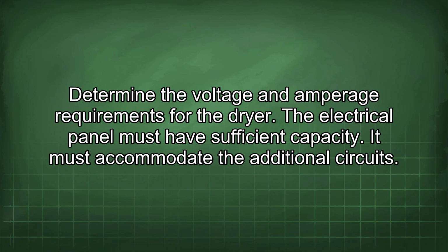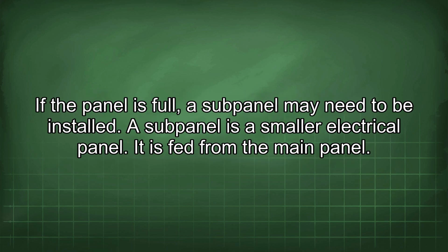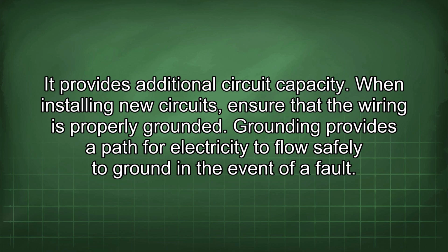The electrical panel must have sufficient capacity. It must accommodate the additional circuits. If the panel is full, a subpanel may need to be installed. A subpanel is a smaller electrical panel. It is fed from the main panel. It provides additional circuit capacity.